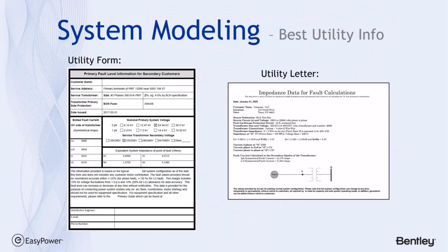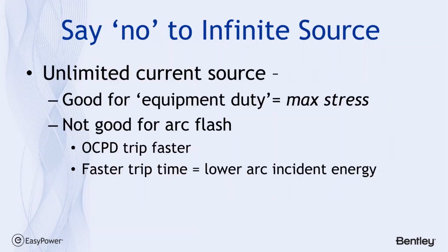Now, the responses you'll get from a utility company can take many forms, and at the very least, you should document it and keep on record what their response is. But these can take a form like the one on the left, where we have different categories and different selections, or a utility letter like the one on the right, where they specifically address what the service is to my location. Very informative, very good information, and in many cases it's more than we need to do the arc flash. But it's helpful in doing other studies, so nothing lost.